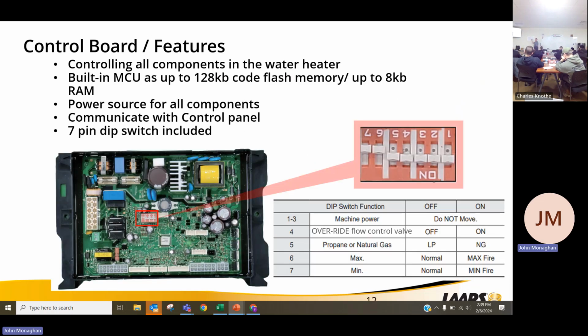So you're going to have your dip switches just like you do on your heat onlys. Min and max fire are going to be used again for testing your combustion. Your override flow valve is going to be for your recirc systems. Depending on whether you're using those crossover blocks, you're going to override your flow valve because you're not quite getting water coming back to the unit. There are crossover blocks like what Watts, I think Moen sells, and I think everyone sells those, where you tie your hot and cold together underneath the lav sink or your furthest fixture. You're basically just pushing hot water into the cold water, and it's not a true recirc. There's going to be a second flow control where it's going to be looking for that recirc to come back. We just have to turn it off so that function actually works.